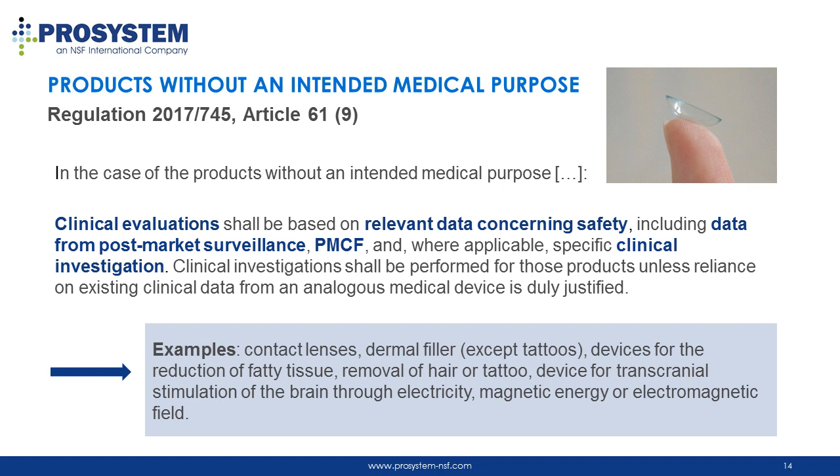Before proceeding to the potential routes to perform a clinical evaluation, you should also consider the following special cases. The clinical evaluation of products without an intended medical purpose, such as contact lenses and dermal fillers, shall be based on relevant data concerning safety, which includes data from post-market surveillance, PMCF, and, if sufficient clinical data is not available, specific clinical investigation. In these cases, the demonstration of clinical benefits should be understood as a demonstration of performance.